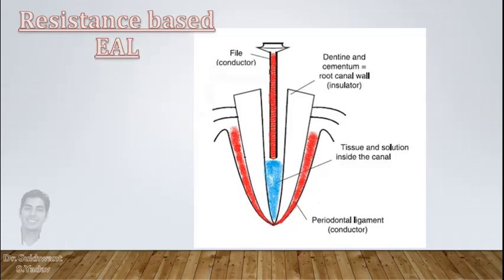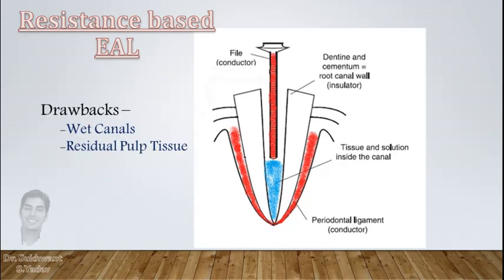But as there can be some tissue or blood or irrigant present in the canal, it leads to completion of circuit before reaching apex and this causes error in reading. So drawback of resistance based apex locator was that they can work in dry canals only.